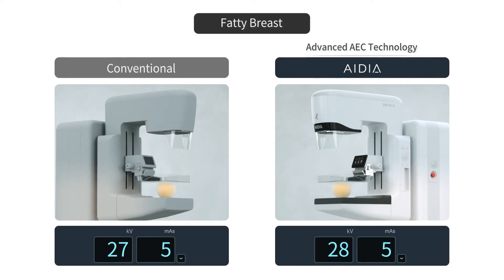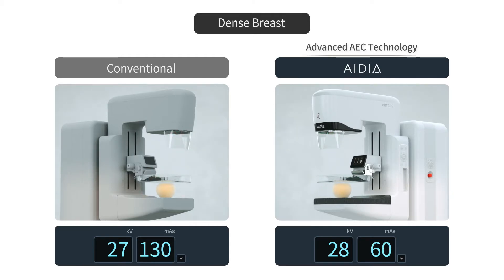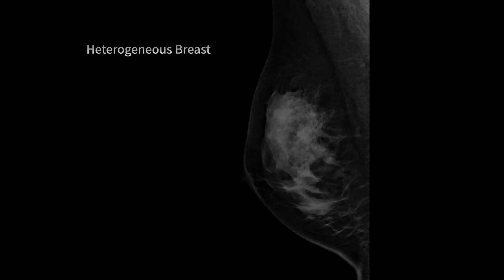AIDIA's advanced AAEC is differentiated from others that only adjust the mAs settings for different breast types. AIDIA's AAEC exposes the right amount of radiation by controlling both the kV and mAs, calculating the patient's breast thickness and density, ensuring consistent high-quality images while maintaining optimized low-dose.